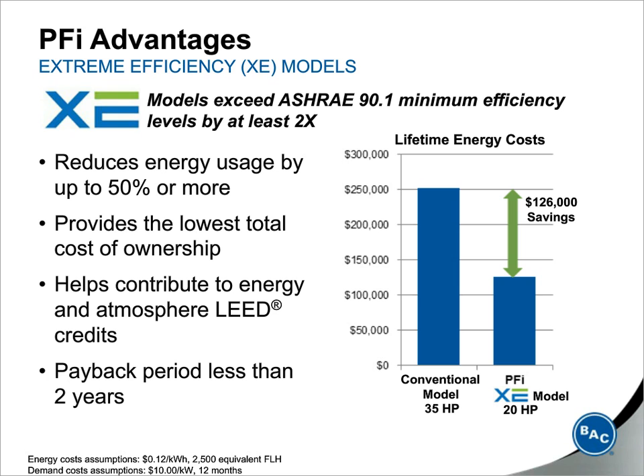So on the right, you can see the cost savings between a model that has the lowest first cost with a 35 horsepower motor and an extreme efficiency model with 20 horsepower. And this evaluation also includes pump horsepower savings as well. The extreme efficiency model, as you can see, saves $126,000 over the life of the equipment. And it's all these different design strategies and technologies that add up and are very important to lowering your total cost of ownership.